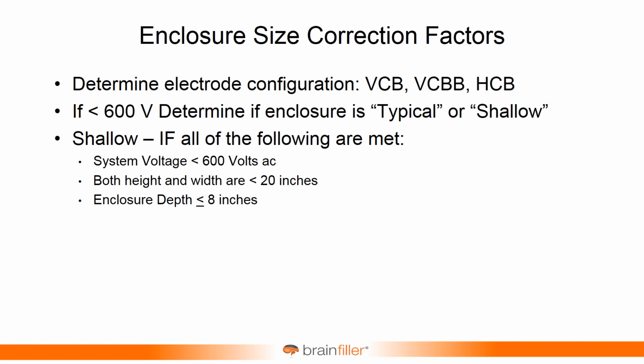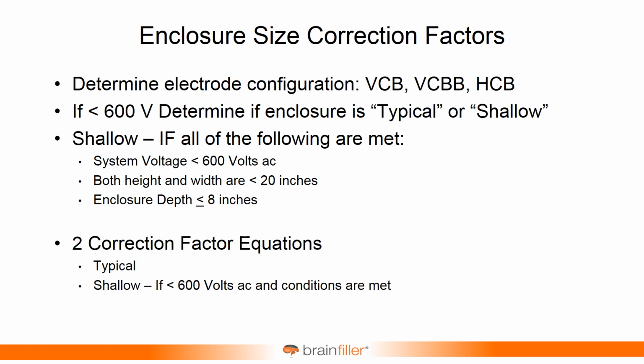So as far as the correction factors, and there's a whole calculation process you go through for this, we have what's typical and what's considered shallow. Typical is most commonly what you're going to be using for low voltage, and for medium voltage up through 15 kV. But again, for low voltage, less than 600 volts, if it's classified as shallow, there's a different adjustment that you can make.